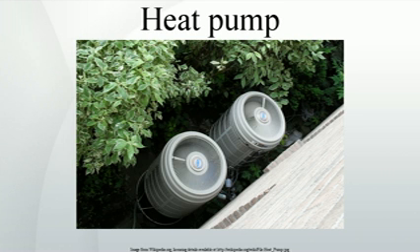Hybrid, or twin source, heat pumps use air when outdoor air is above 4 to 8 Celsius, 40 to 50 Fahrenheit, depending on groundwater temperature. When air is colder, they use the ground source. These twin source systems can also store summer heat, by running ground source water through the air exchanger or through the building heat exchanger, even when the heat pump itself is not running.